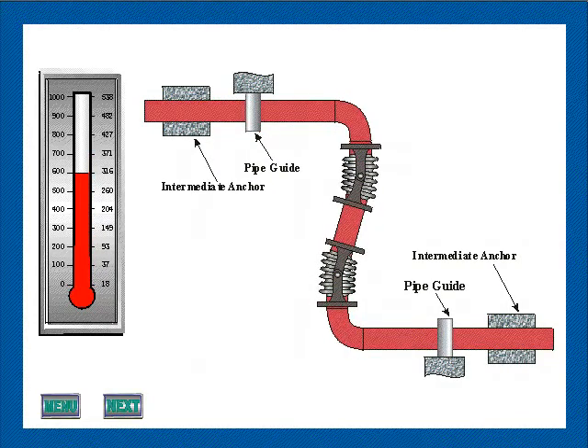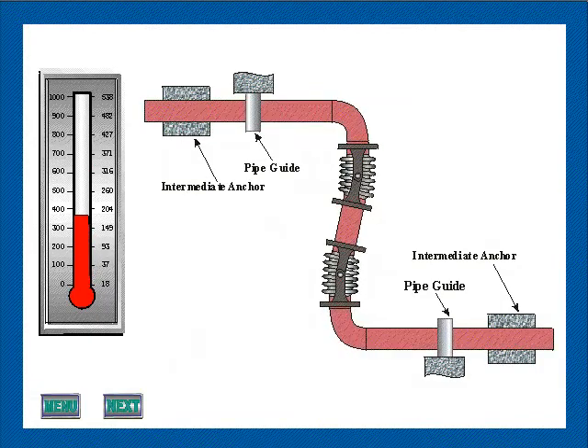This effect can be minimized by cold springing the expansion joints 50% of the full rated deflection.